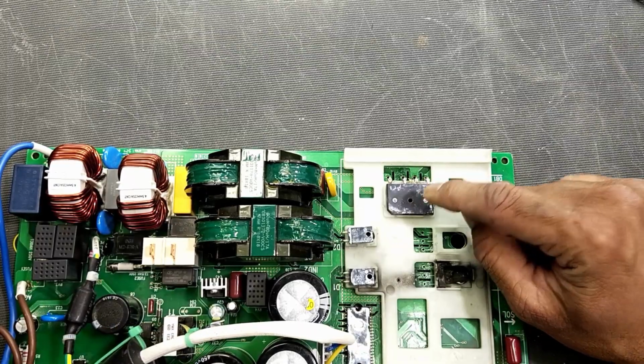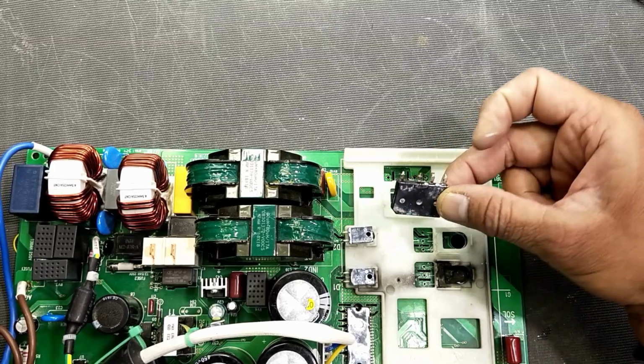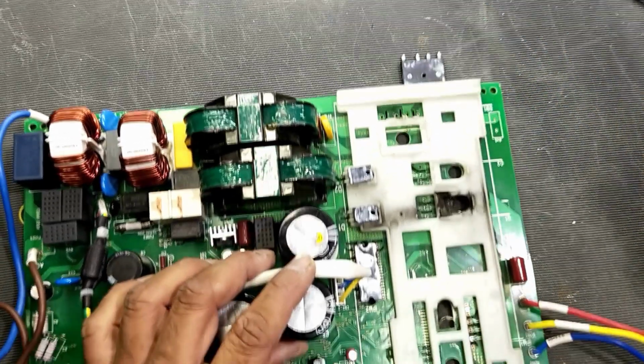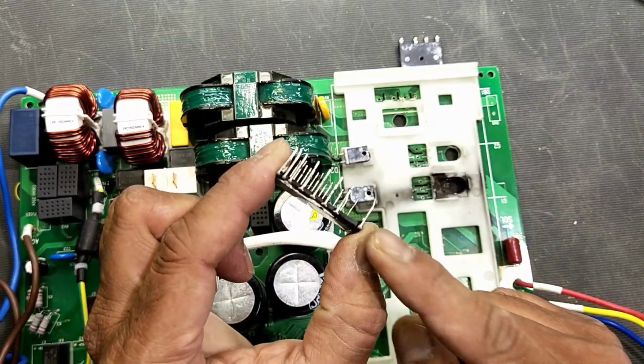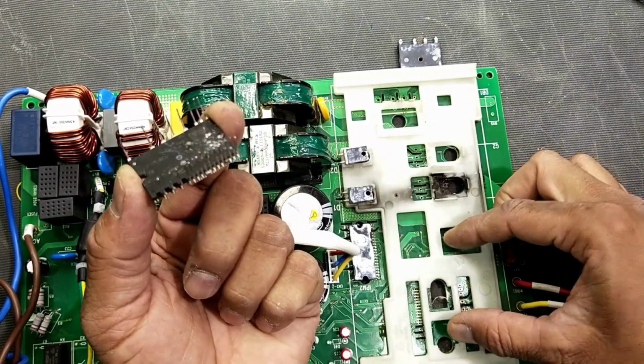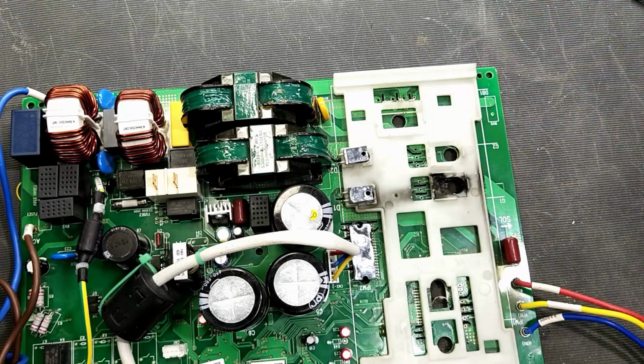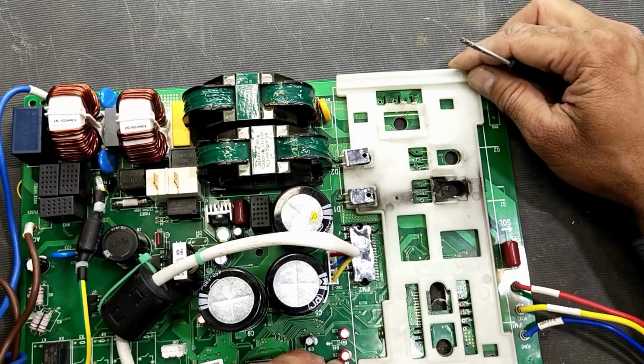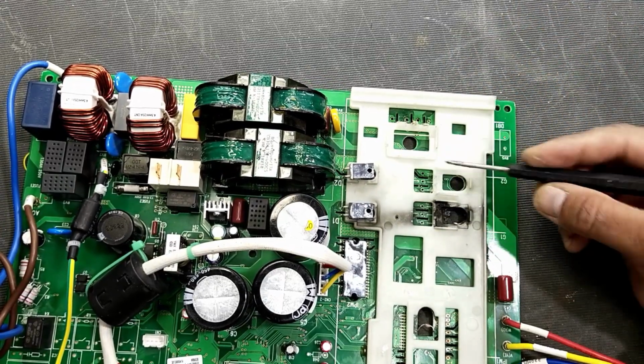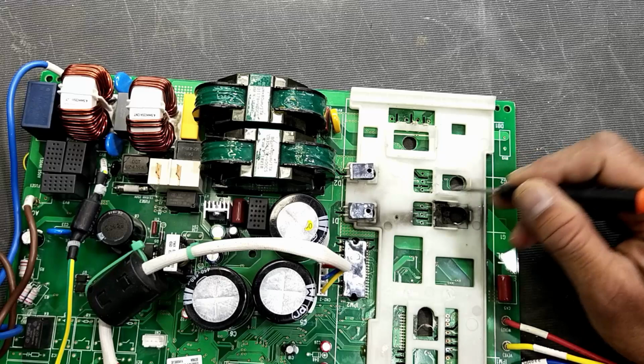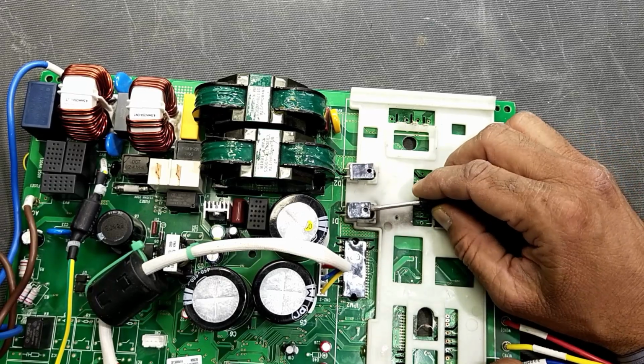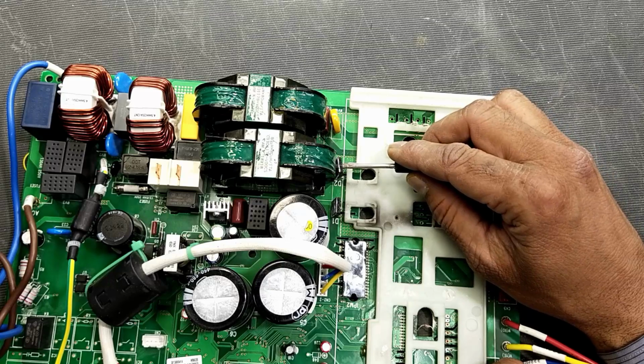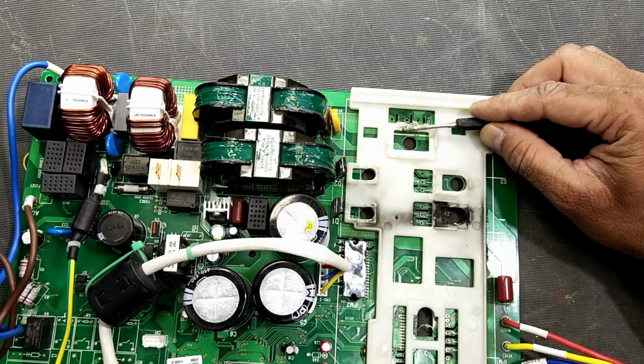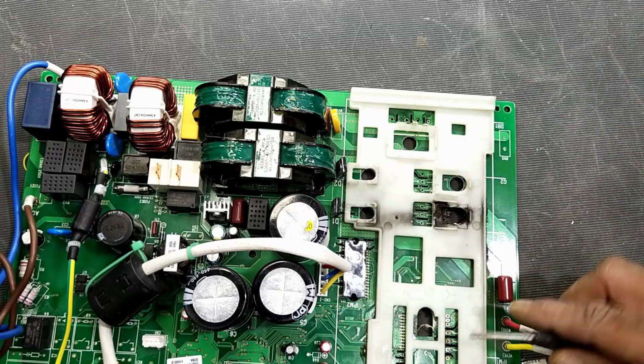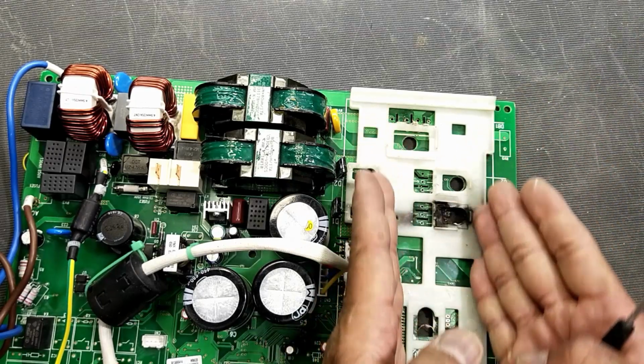Last video we detected that the bridge rectifier is short circuit, so I disconnected the bridge rectifier from the circuit, and I also removed this IPM module from the board. We have to inspect this portion before going to the further repair. We have to remove these IGBTs and the diodes. Just pull out here, remove bridge rectifier, IPM, because these are connected on these plastic mountings.